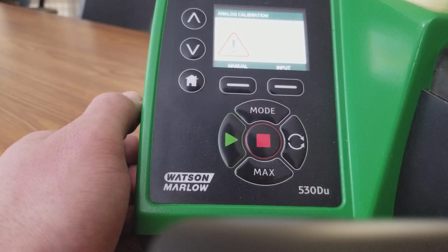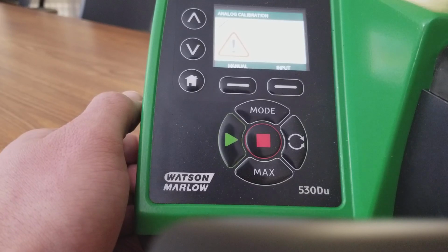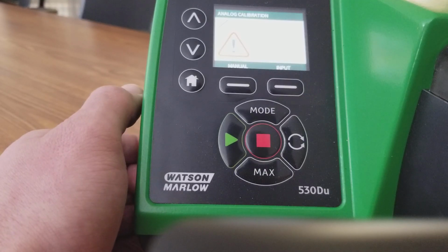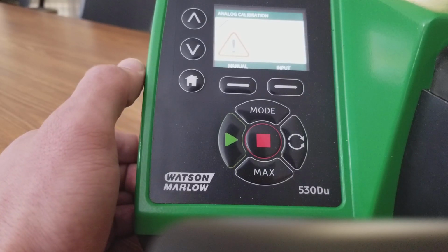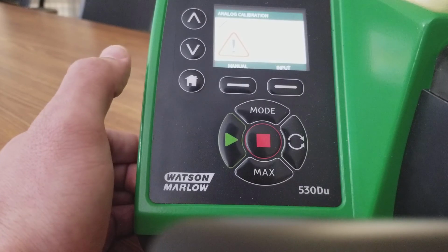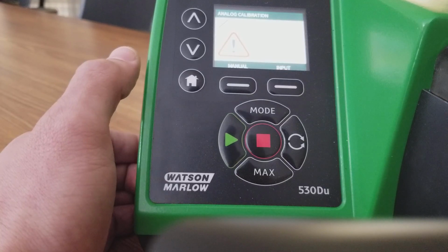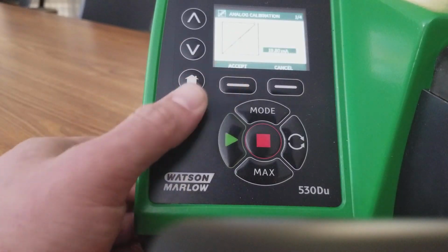If you put SCADA into manual, you can use 0 to 100%, 4 milliamps being 0 and 20 milliamps being 100%. When they send the signal, you would select input. That way, if they've got a milliamp above 4, you could set that as your 0. But at this time we'll be using manual.